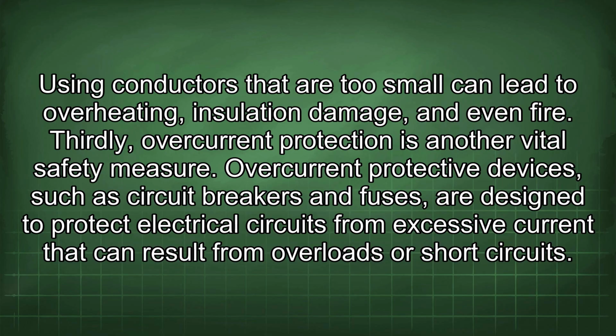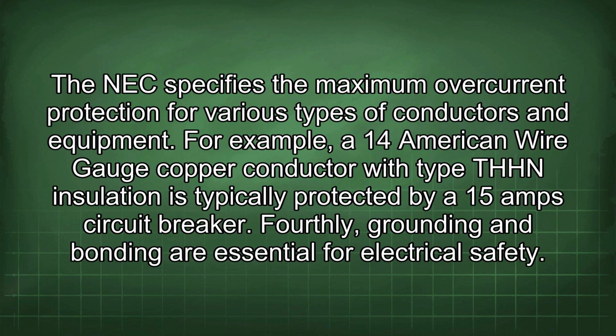Thirdly, overcurrent protection is another vital safety measure. Overcurrent protective devices, such as circuit breakers and fuses, are designed to protect electrical circuits from excessive current that can result from overloads or short circuits. The NEC specifies the maximum overcurrent protection for various types of conductors and equipment. For example, a 14 American wire gauge copper conductor with type THHN insulation is typically protected by a 15 amp circuit breaker.